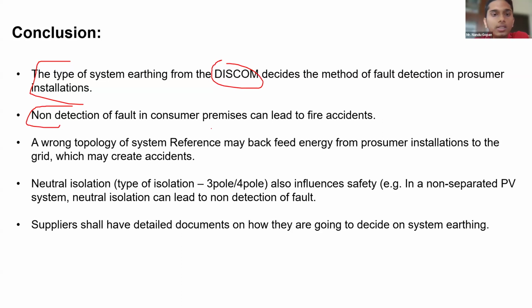And if you use a wrong system topology, suppose the neutral conductor is not done properly, or you select a wrong system referencing conductor or wrong system referencing topology and changeover, and you don't coordinate them properly, there can be backfeed from the PVI to the grid. That can create issues not only in your installation but also in others' installations. If there are any other nearby consumers of the discom, it will create issues on their side.